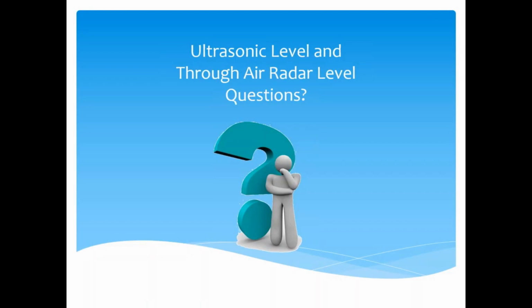Okay, for water-based applications without foam, do you recommend ultrasonic or radar? I would recommend ultrasonic for nearly all water-based applications without foam, unless it happened to be a high temperature or pressurized situation. But traditionally for me, a water-based application is going to be an ultrasonic application.